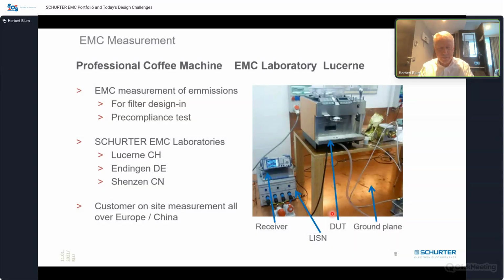What we do is we just do pre-compliance measurement. So we are not a fully accredited laboratory, we do pre-compliance test. As you can see here on that picture, this is a professional coffee machine standing on a wooden table with a copper ground plane on the floor. And then you see here the line impedance stabilization network and the spectrum analyzer here on top, measuring the noise coming, in this case, conducted via cable out of the coffee machine.